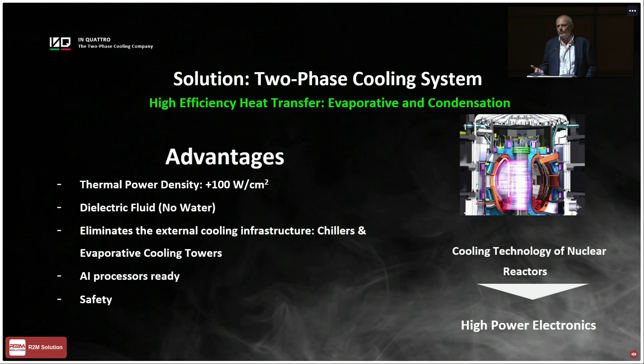Okay, so what is possible to do with this technology? The PUE, the power usage effectiveness, can be reduced from the range between 1.5 and 2.5 for a traditional cooling system. This depends on the technology used in the data center and the quality of the cooling system. It's possible to reduce this down to a theoretical limit of 1.05, between 1.05 and 1.2. This range depends strongly on the configuration of the data center.